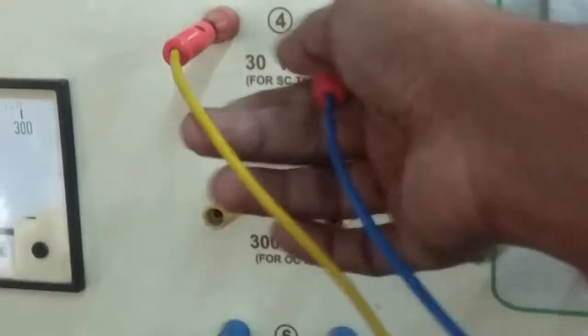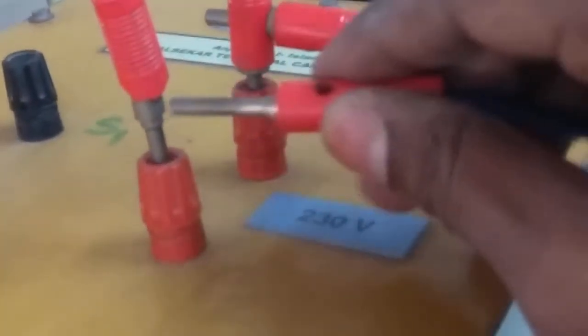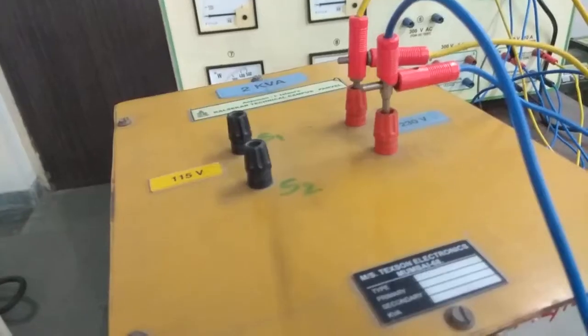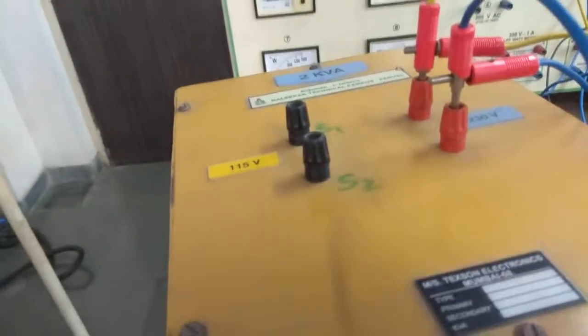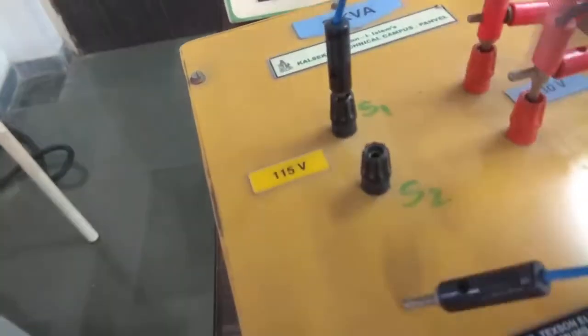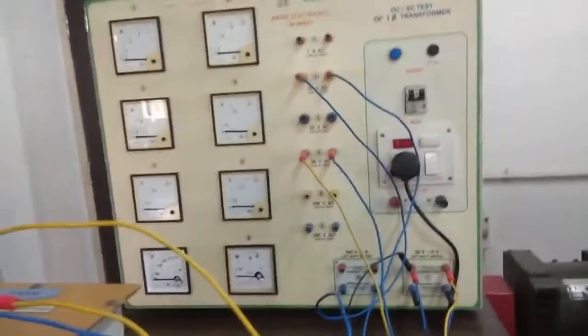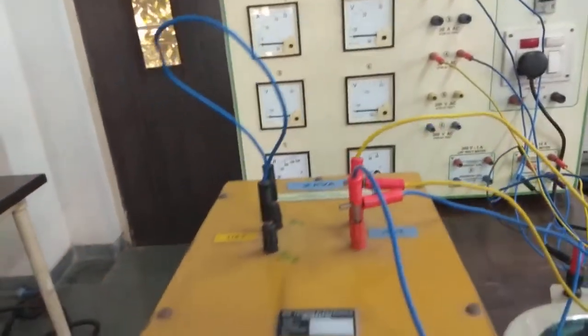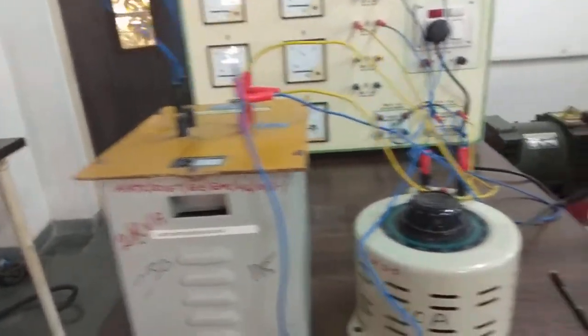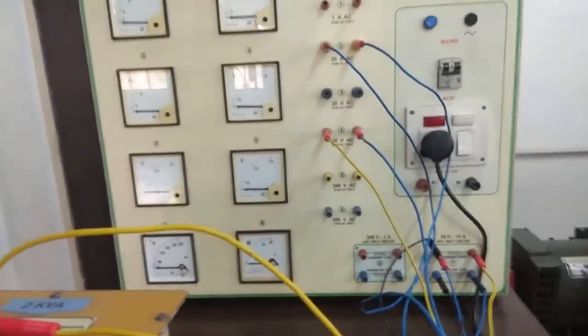Now we will connect the low range voltmeter in parallel to the HV side of the transformer. Since this is a short circuit test, we will take a wire and short the LV side of the transformer. Now you can see our connection is completely ready. We are giving the supply to the variac, and from the variac we are giving the supply to the transformer via ammeter, voltmeter and wattmeter.